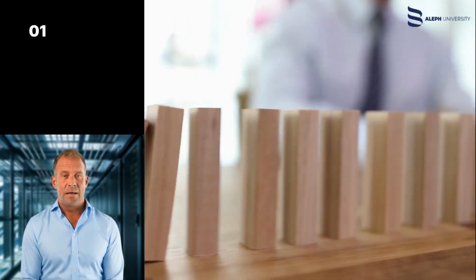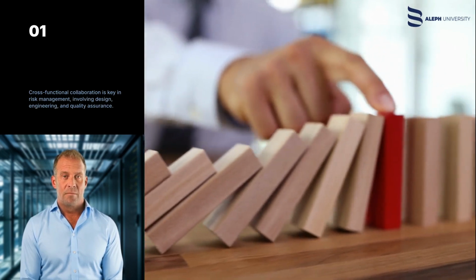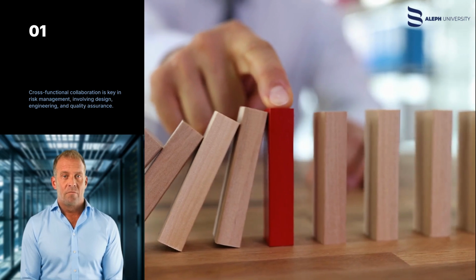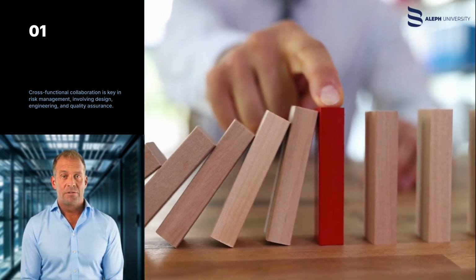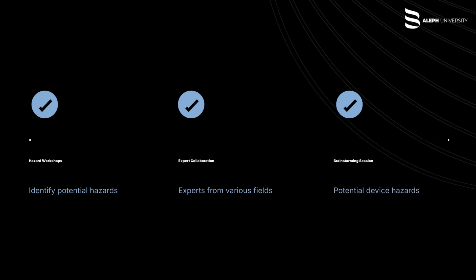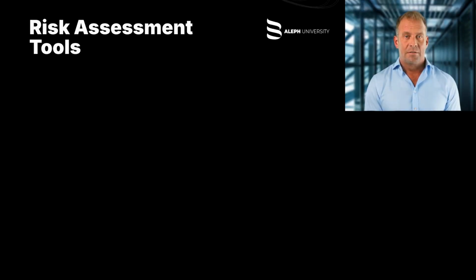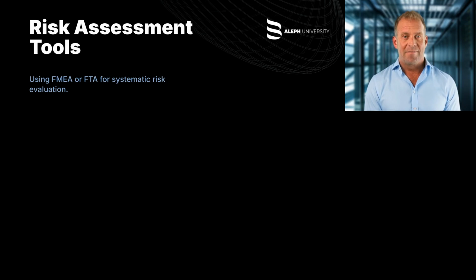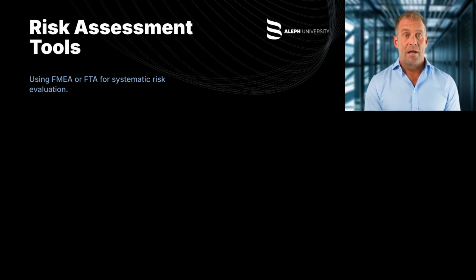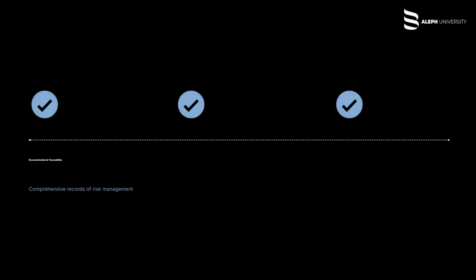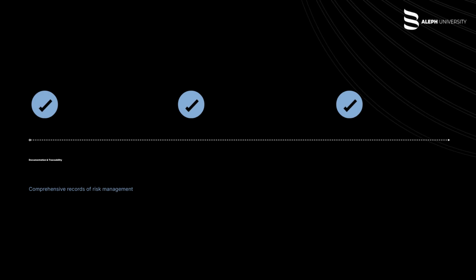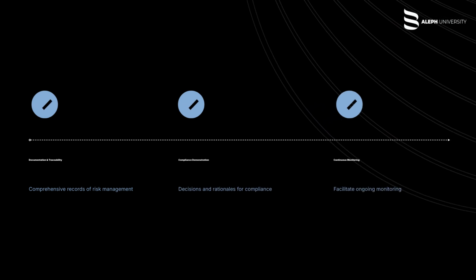Practical application of risk management. Implementing an effective risk management process involves cross-functional collaboration among various departments, including design, engineering, quality assurance, regulatory affairs, and post-market surveillance. Practical steps include hazard identification workshops, bringing together experts from different disciplines to brainstorm potential hazards associated with the device. Risk assessment tools utilizing methodologies such as failure modes and effects analysis, FMEA, or fault tree analysis, FTA, to systematically evaluate risks. Documentation and traceability, maintaining comprehensive records of risk management activities, decisions, and rationales to demonstrate compliance and facilitate continuous monitoring.